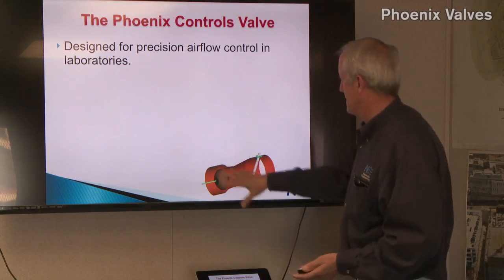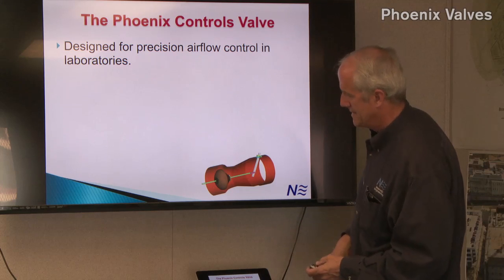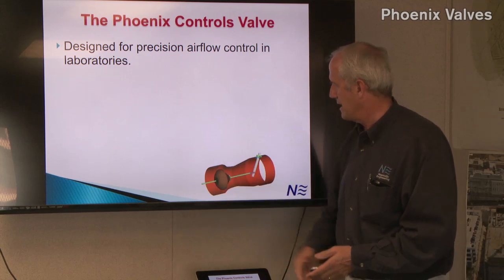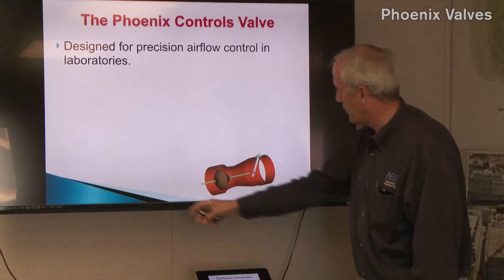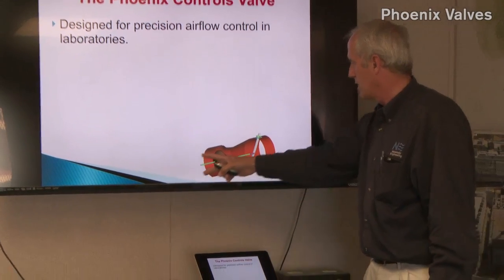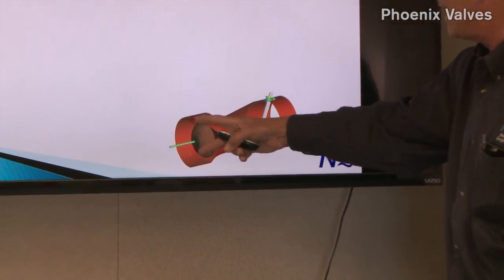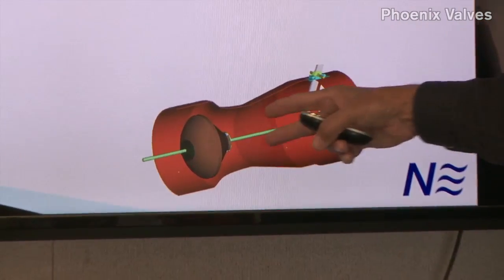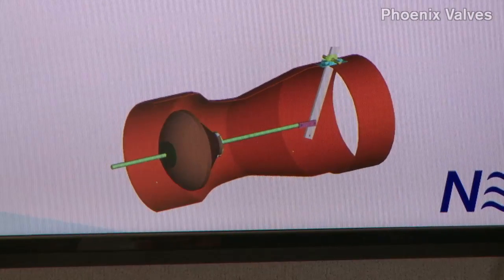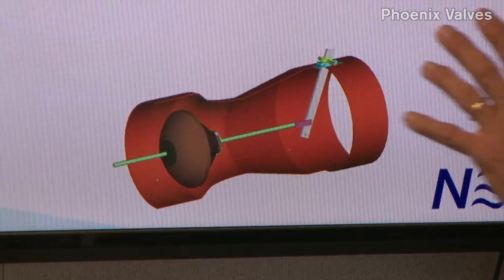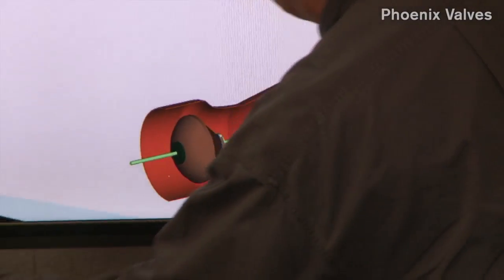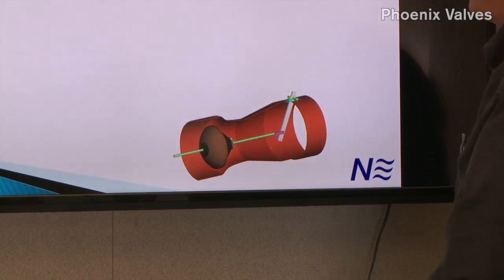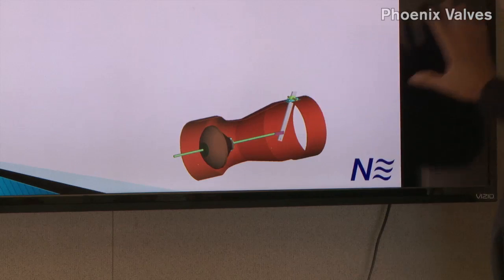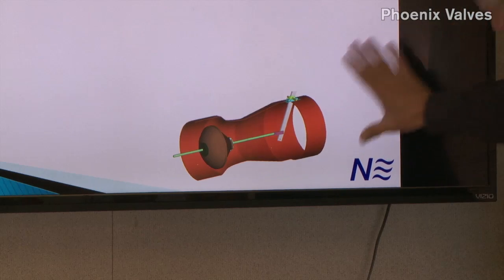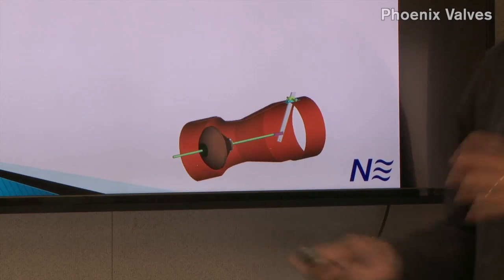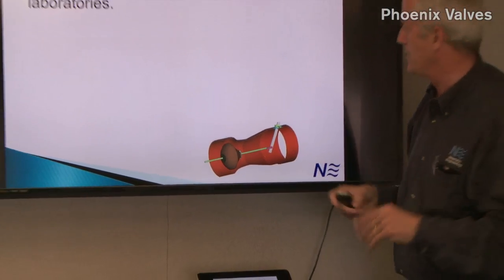I want to talk about the valve. This is what a cutaway of a Phoenix valve looks like. I don't know if you've seen it before, but the air enters on the left, goes through the valve around this kind of hemispherical cone, through the throat of this venturi, and out that way. If this were a supply valve, the fan would be on this side, pushing air through our valve. If this were an exhaust valve, the fan would be on the right side, sucking air through our valve. But the physics, the operation of the valve is the same either way.